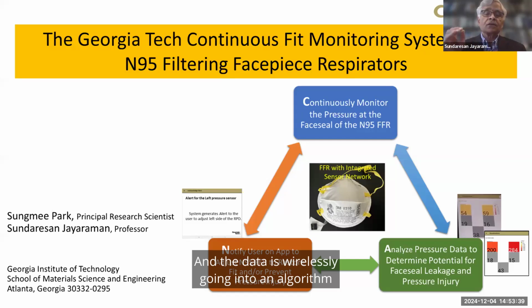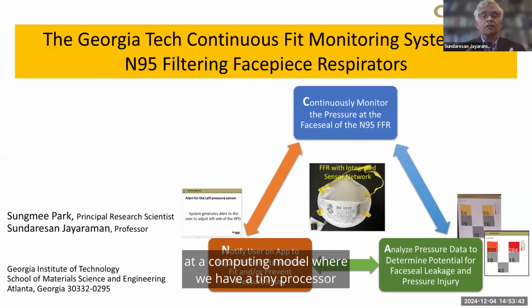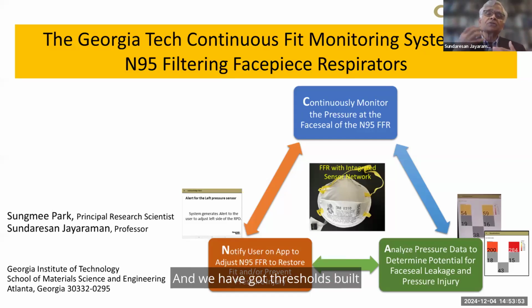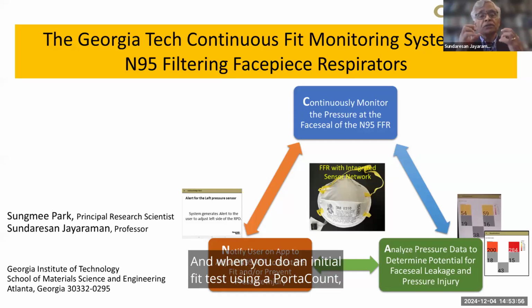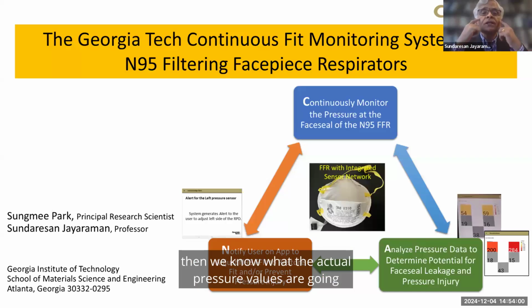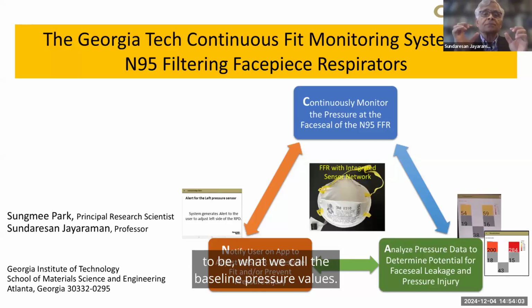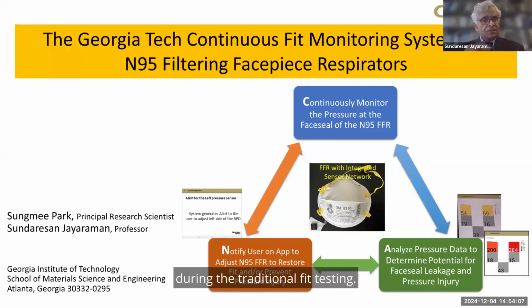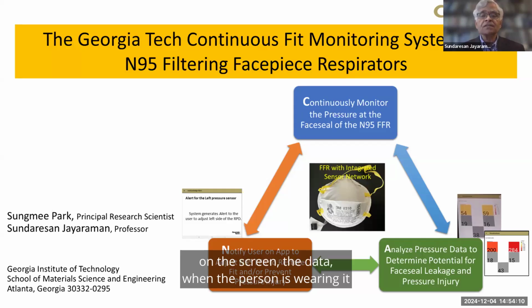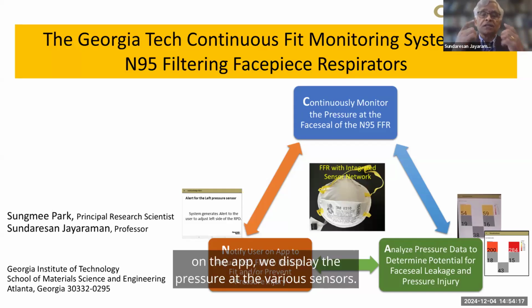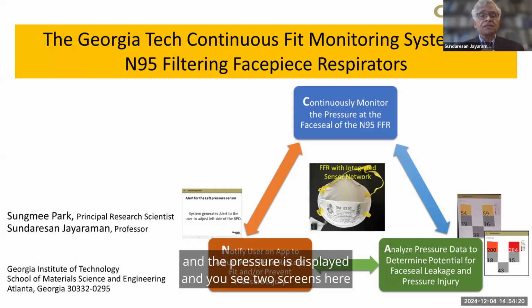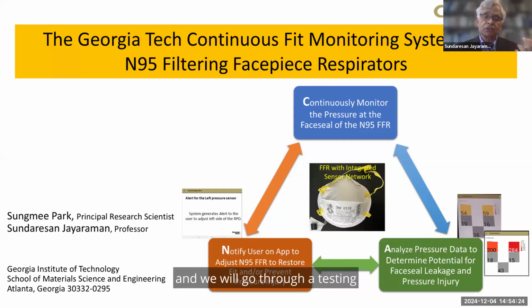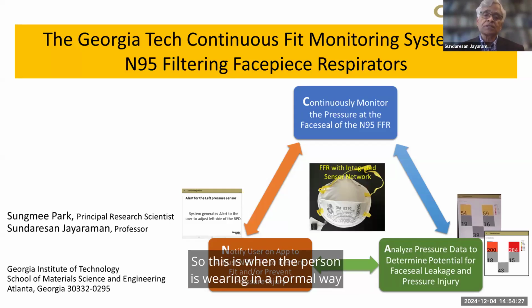The data is wirelessly going into an algorithm and a computing model where we have a tiny processor. If you look here in the second part, that is where we are analyzing the pressure data in real time, and we've got thresholds built into it based on the facial profile. When you do an initial fit test using a PortaCount, then we know what the actual pressure values are going to be, what we call the baseline pressure values. That information is captured during the traditional fit testing. Then, as you can see here on the screen, when the person is wearing it, on the app we display the pressure at the various sensors. In this case, we've got 5 sensors, and the pressure is displayed. You see 2 screens here, and we will go through the testing that we did with the PortaCount in a minute. So this is when the person is wearing it in a normal way.